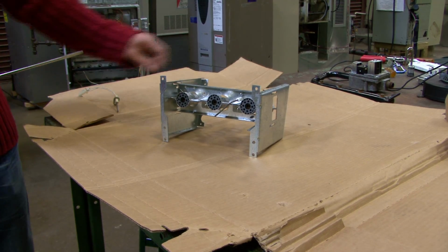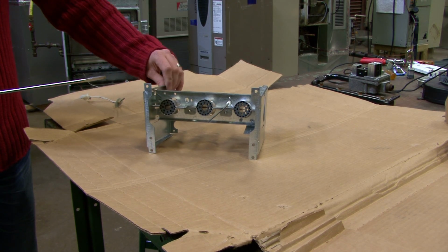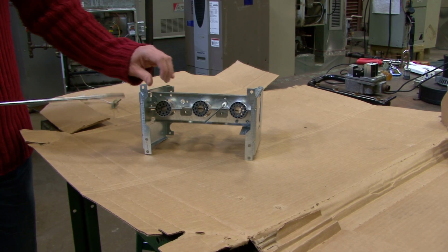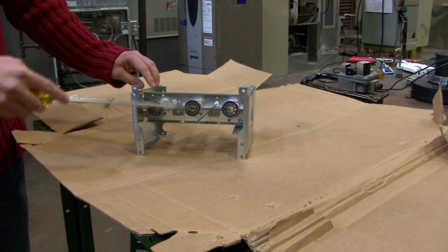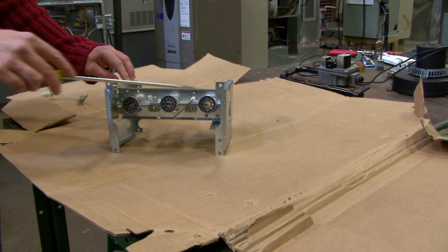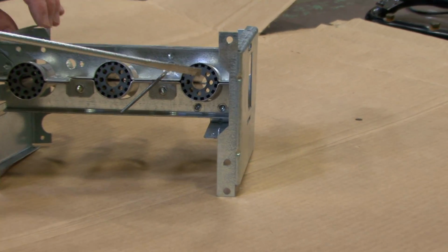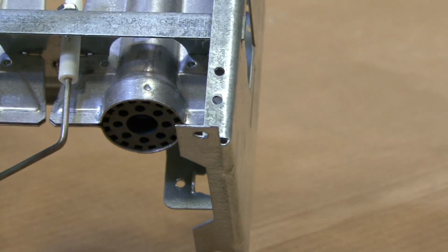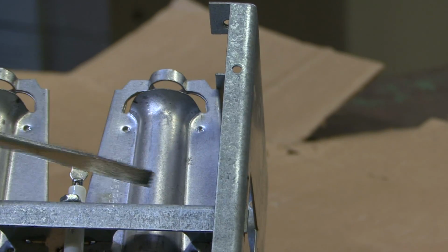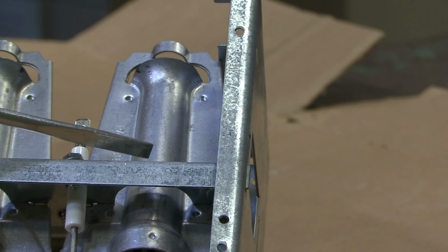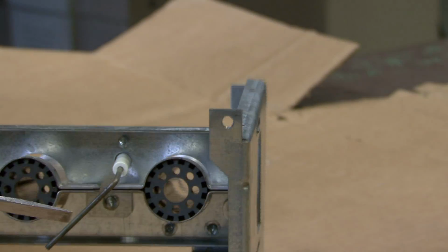Here's a close-up of the burners removed from a furnace. This is a 3-burner assembly. It could be up to 6 or as little as 2. But here you can see the burners themselves. On the end, they kind of look like a jet engine when it burns. Again, the flame typically burns here on the end of the burner, not inside the metal part of the burner. If we have some flame inside the metal part of the burner, these things will deteriorate and melt, and that is an undesirable condition.